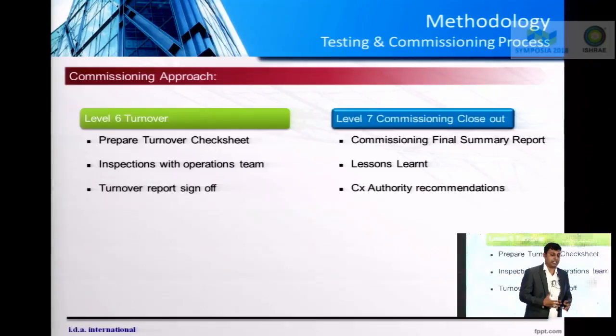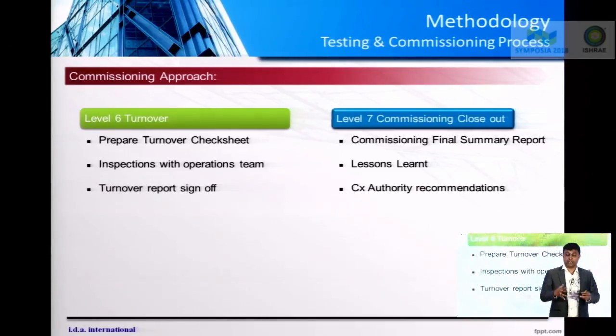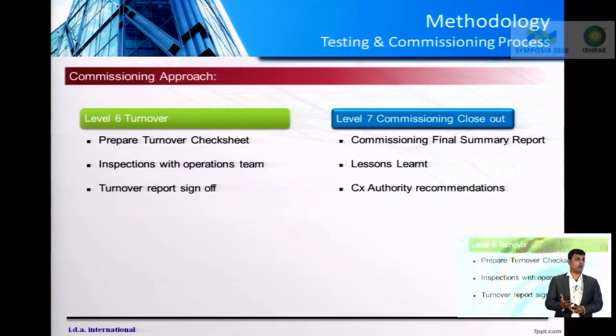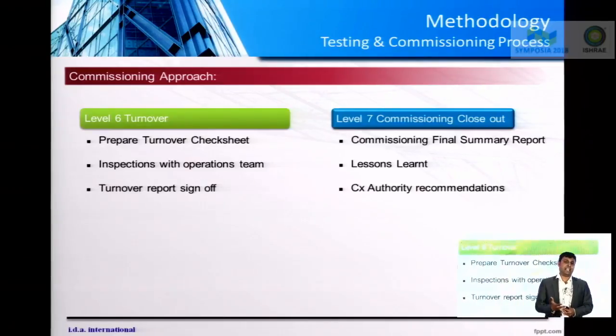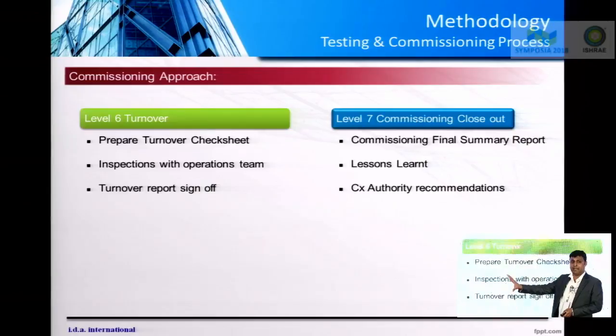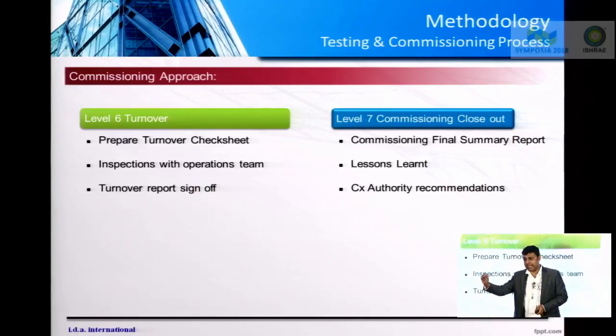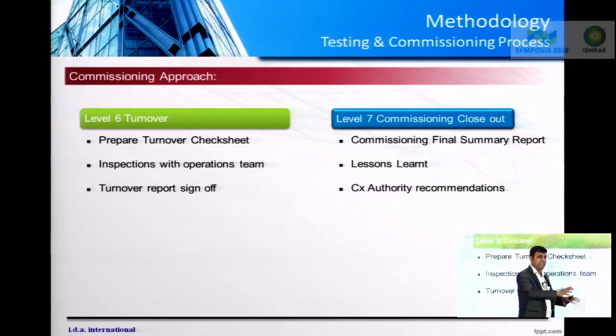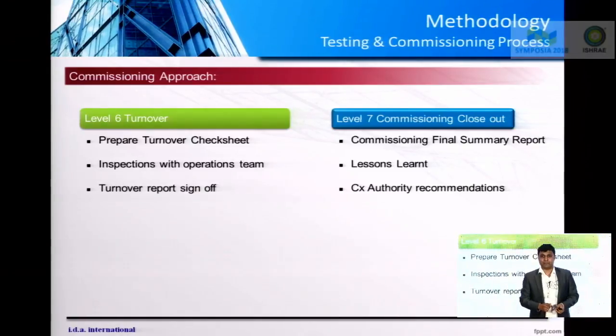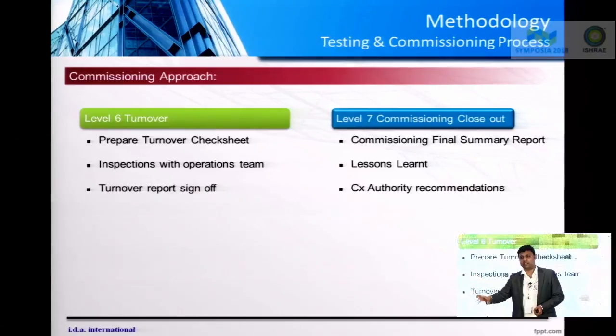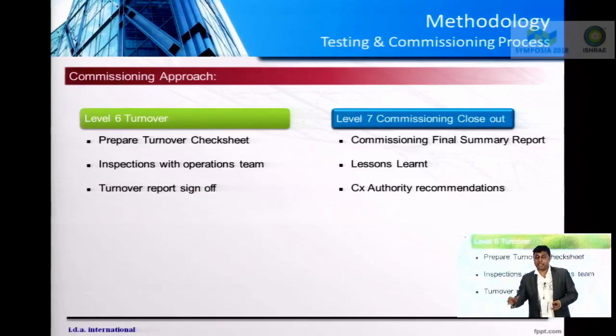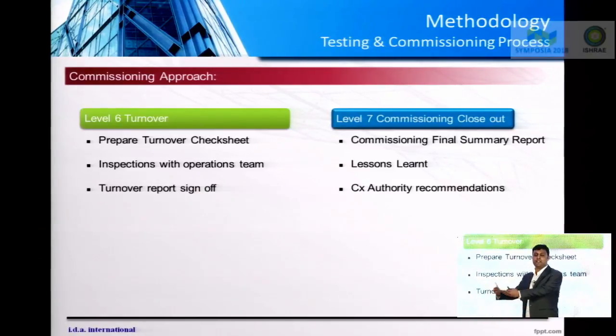This inspection includes verifying: the commissioning team will verify the O&M documents, they will verify the as-built drawings, and they will also verify if every single equipment is kept at the right design conditions. Because when you do so many testing activities, you tend to change the set point of the equipment. You change the set point of CRAC units, you change the breaker settings, but you cannot hand over the facility in similar fashion to the operations.